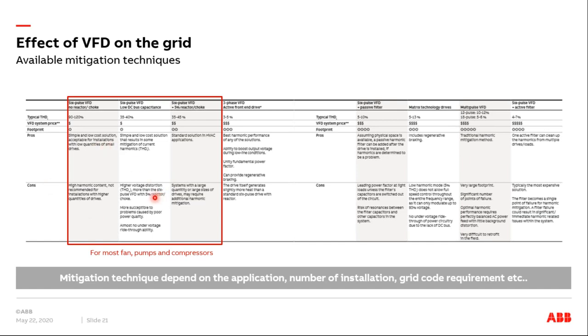But if you go to higher power and if you're using a larger number of drives, then there would be a requirement from the grid to do that. And also it's in the best interest of the customer to do it, because it's affecting his or her other systems. So the most common way of mitigating this harmonics effect on the grid side is just using 5% or 3% chokes, what we call reactors or chokes, which reduce the harmonics to an acceptable level. This is also a cheaper option, because cost is always a factor. There are a lot of different ways of addressing these issues, but this is one of the cheapest options out there, and it's commonly used in most fan, pump and compressor applications.